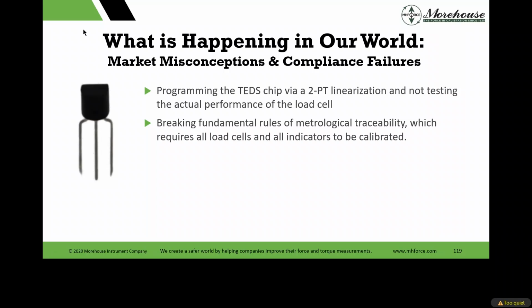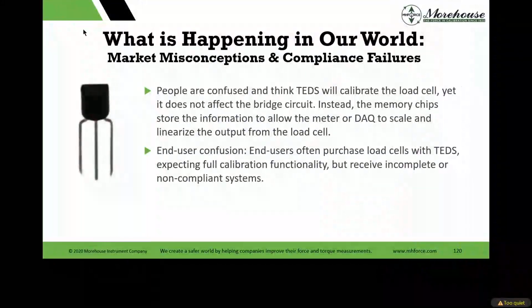And when I say you're breaking the rules, I mean they buy indicators and they never calibrate the indicators. The assumption is my indicators are perfect. I hook the TEDS chip up, I put it in the load cell, the indicator reads what it should read. No, what needs to happen is that the indicator needs to be calibrated with the load cell, or separately with its own chain of traceable measurements and uncertainty analysis. So that in itself makes TEDS a bit of a pain in the butt.